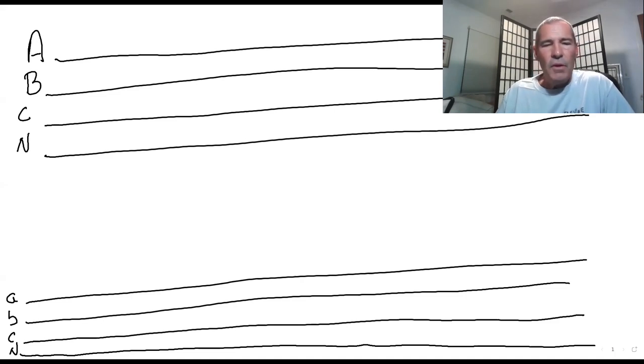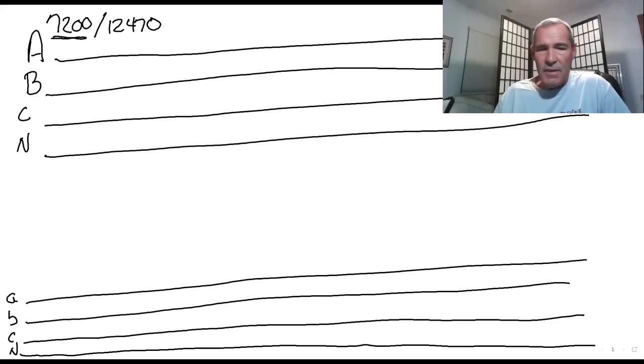All right, so the Open Delta bank, as far as what's on the template, the primary is 7,200 and 12,470. Now, when I draw it like that, what is the first number? Phase to neutral. Correct. And this helps every single time. Now that I'm getting started, I'll come out to the end of the neutral line right over here on the right-hand side. And I'll just go ahead and ground it, get that over with. They all are grounded neutrals.